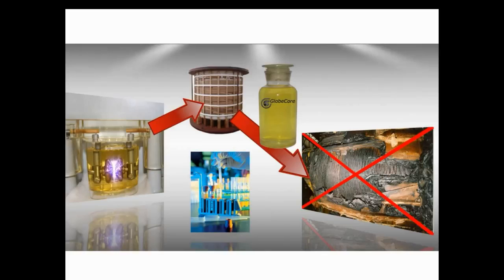I think that when we speak about oil function, first of all you think about dielectric strength and heat transfer. But in regeneration, solid insulation protection is extremely important, as it is the reason for the technology to arise.